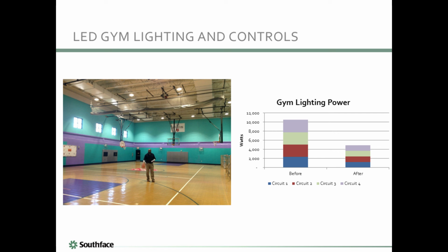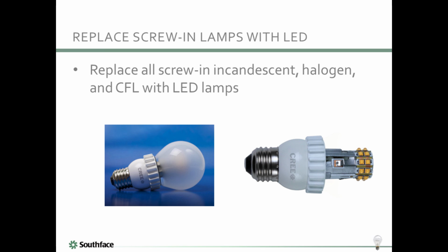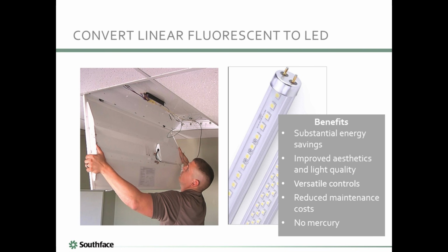Adding dimming capabilities to gymnasiums also allows for greater flexibility of space use, since you can use dimming for events, movies, and other functions. LED fixtures are fully dimmable and pair well with photosensor controls for daylight harvesting applications. If you have natural daylight coming into your gymnasium, LED fixtures with daylighting controls can save a lot of energy. So in this project, 400-watt metal halide fixtures were converted to 240-watt LED fixtures, along with dimming controls and occupancy sensor controls.